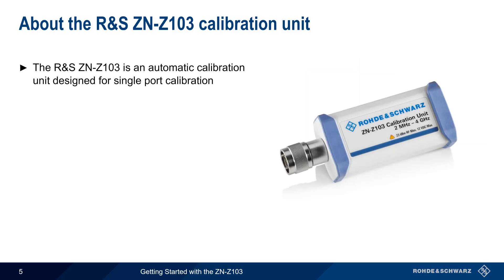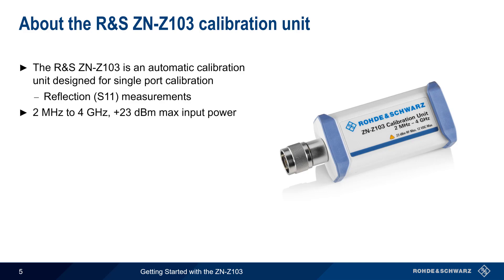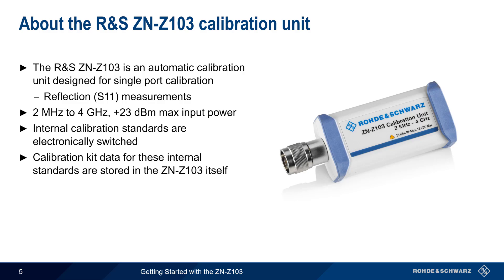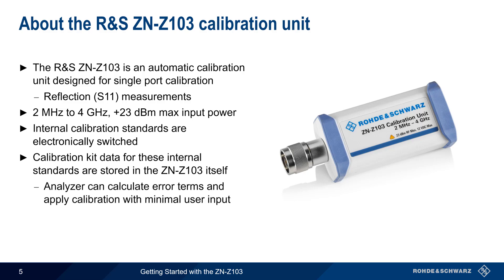The Rohde & Schwarz ZN-Z103 is an automatic calibration unit designed for single-port calibration, that is when making reflection or S11 measurements. It covers a frequency range of 2 MHz to 4 GHz and has a maximum input power of +23 dBm. Its internal calibration standards are electronically switched, which helps to reduce wear and maintain accuracy. Like most other Auto-Cal units, the calibration kit data is stored within the ZN-Z103 itself, meaning the attached analyzer can calculate error terms and apply calibration with minimal user interaction.